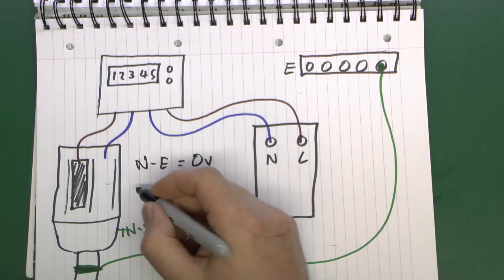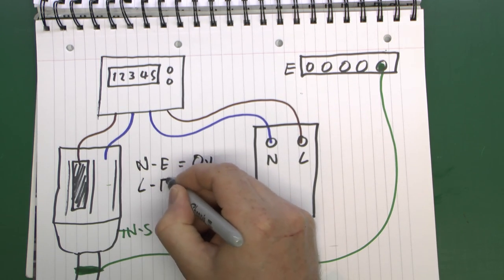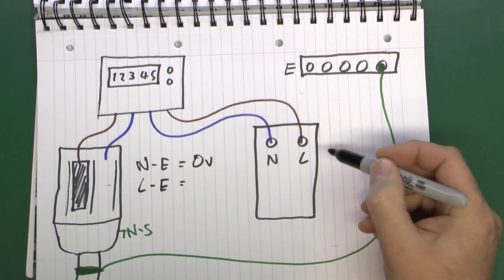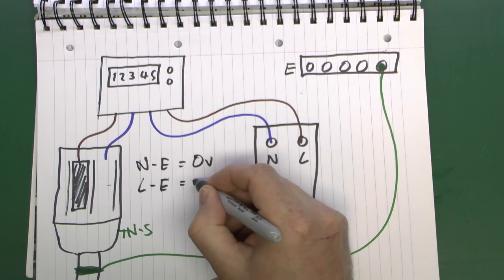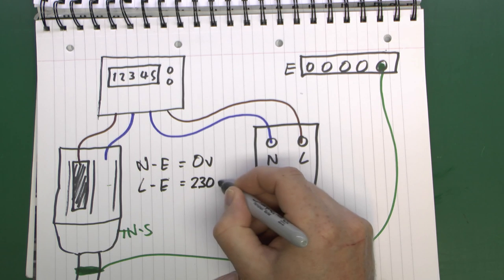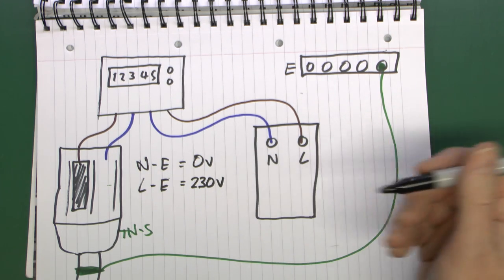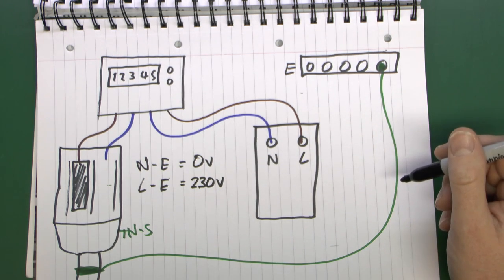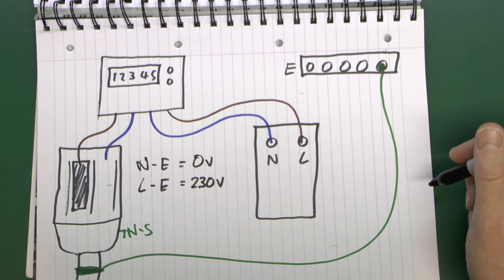And between the line and the earth, you should have the full mains voltage which in the UK is supposed to be around 230 volts. But in reality it can be somewhat higher than that and it usually is, typically in the sort of 240 to 245 kind of area.